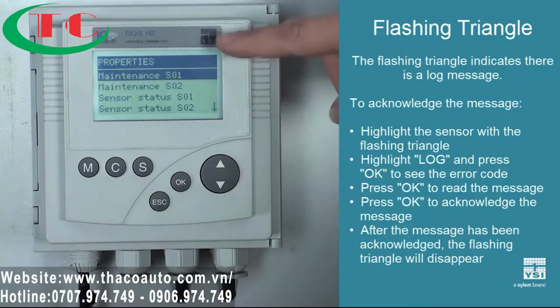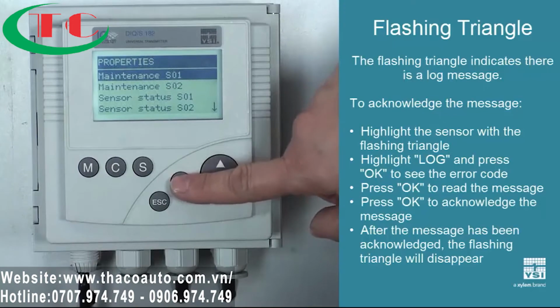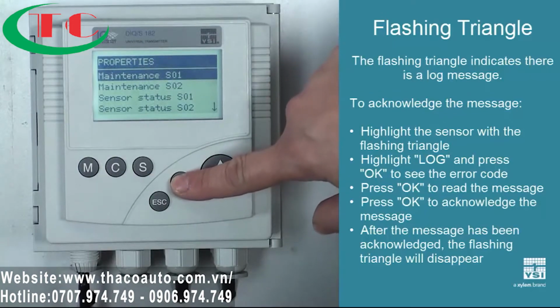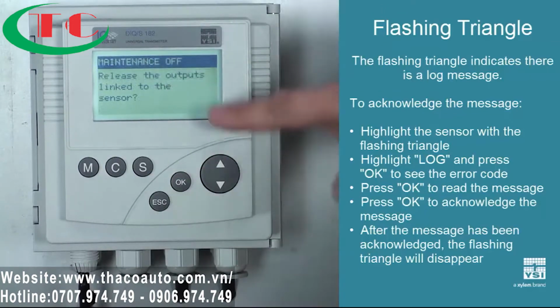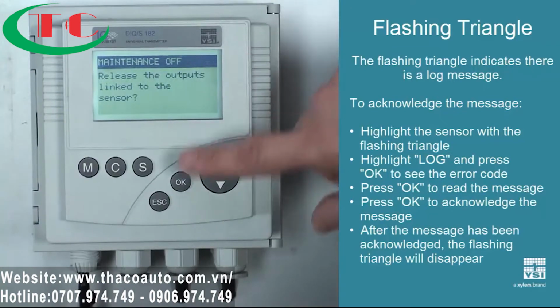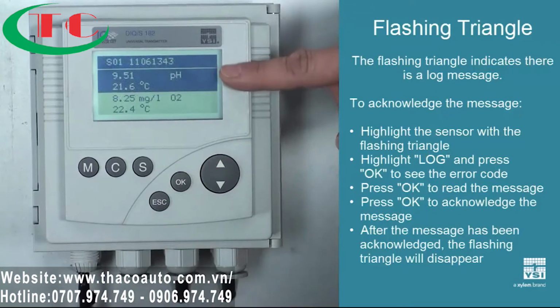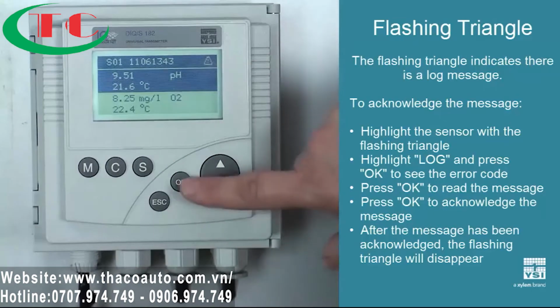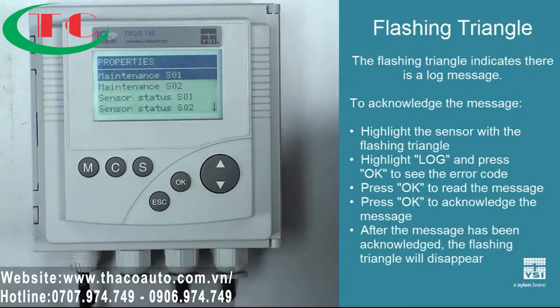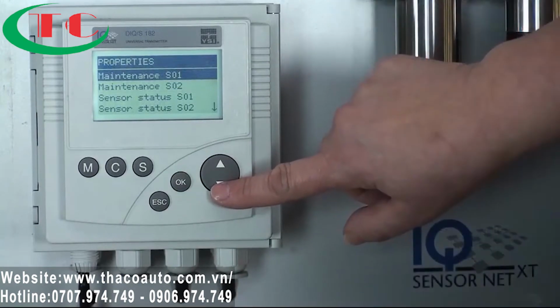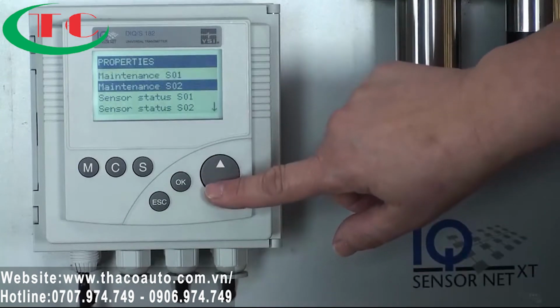I want to take it out of maintenance mode. I'll go back again. Property screen, maintenance, S01 meaning sensor 1. Press OK. It says release the outputs linked to this sensor, and press OK, and once again we got rid of the flashing. So going back into the OK, that was maintenance on sensor 1. We could do the same on sensor 2.